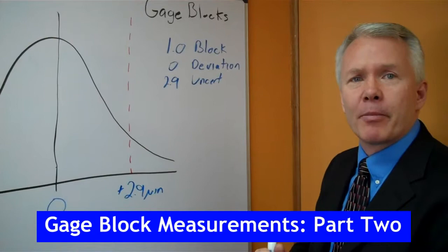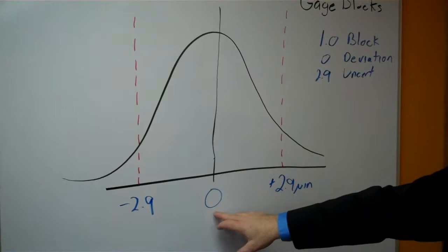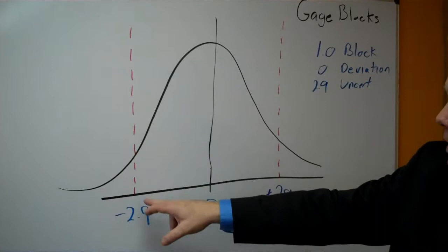I'd like to show you graphically what that means, so it might make a little more sense to you. So if we try to graph a gauge block calibration here with the deviation being zero, this being plus 2.9 millionths, and this being minus 2.9 millionths, that's the spread of our uncertainty.